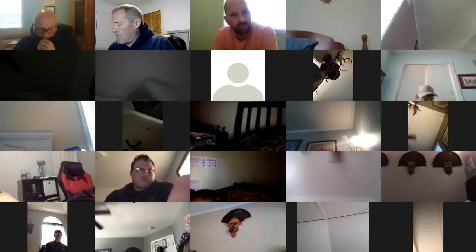The big common error, the big thing that you would assume is if you hear a dispatcher over a radio, one person at that location is in control. So let's say Robbie is in control. He's in the truck. I'm up in the bucket. And Robbie gets the command from dispatch, I'm ready for you to close the switch at pole 1, 2, 3, 4. He needs to read back that command to the dispatcher. The dispatcher needs to confirm with him that he received that command. And then he's going to give me instructions to open or close the switch.